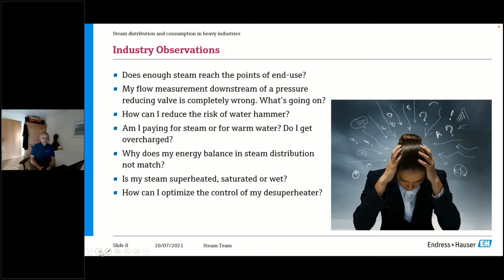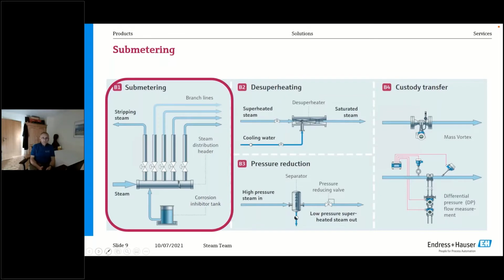We first are going to talk about submetering. So submetering means you have your steam distribution header, and from that you pick the steam, you're going to your own consumption also. So you have stripping steam, for instance, that is going back to the boiler house, or also steam for heating your hot well, for instance, and then you're distributing the steam to various end users. Desuperheating, we're going to come to that later on.